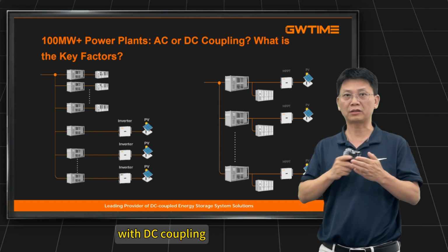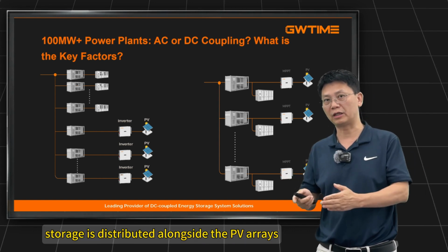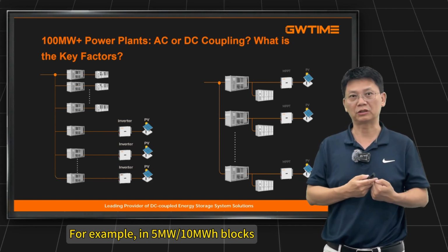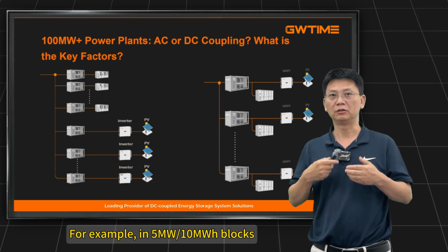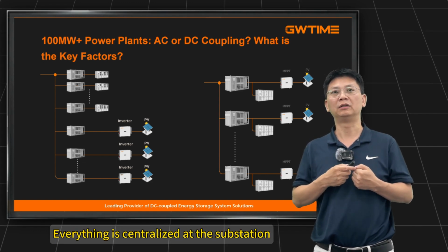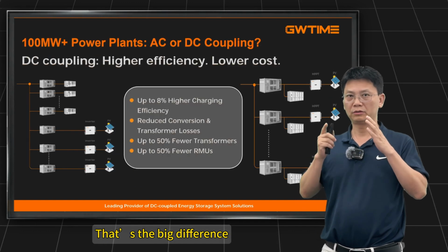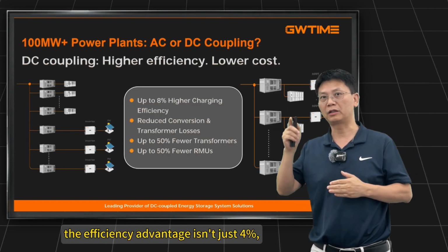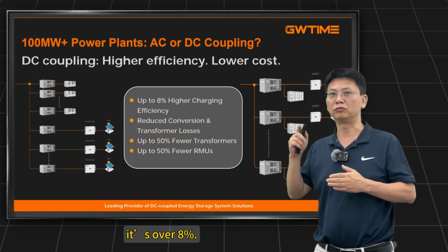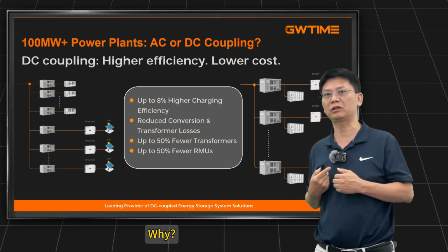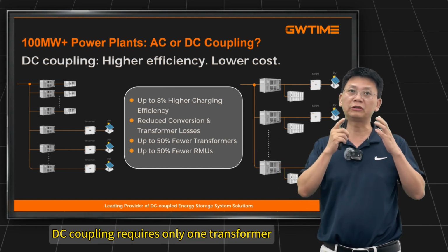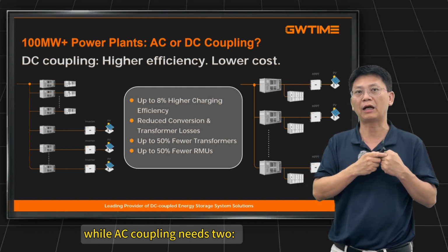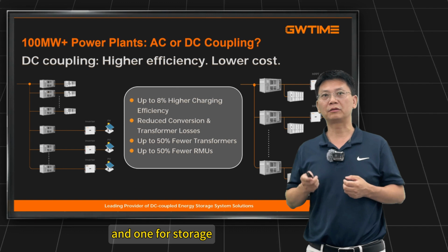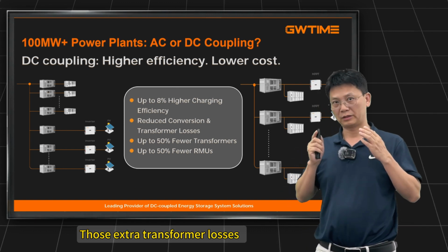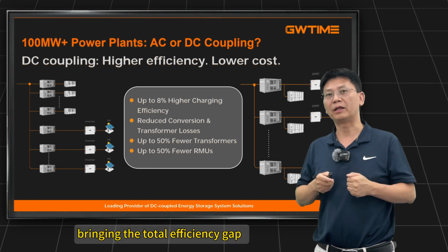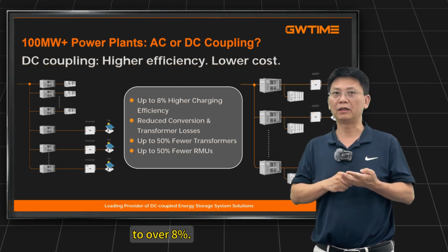Just a heads up, with DC coupling, storage is distributed alongside the PV arrays, for example, in 5 megawatts/10 megawatt hours blocks. Traditional AC coupling, everything is centralized at the substation. That's the big difference. For these giant plants, the efficiency advantage isn't just 4%, it's over 8%. Why? Look at the diagram. DC coupling requires only 1 transformer, while AC coupling needs 2, one for the solar side and 1 for storage. Those extra transformer losses account for another 4%, bringing the total efficiency gap to over 8%.